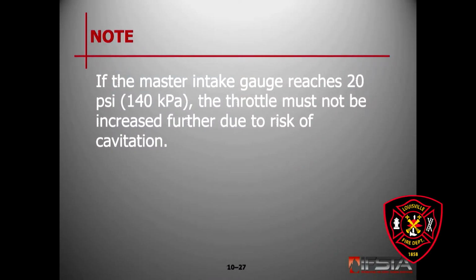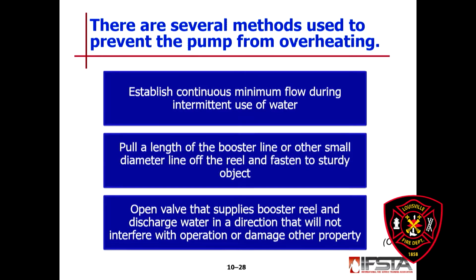We've talked about this already—we do not let that intake gauge slip under 20 psi. There's danger of cavitating the pump, danger of collapsing the supply line, and danger of collapsing a water main.